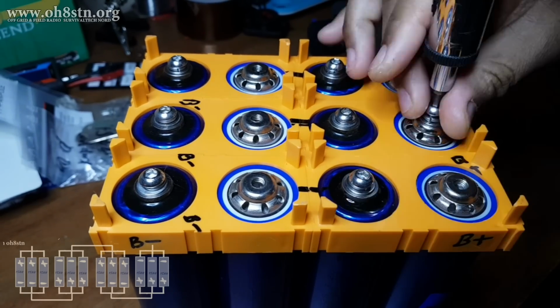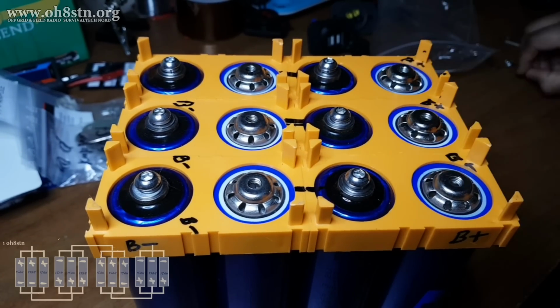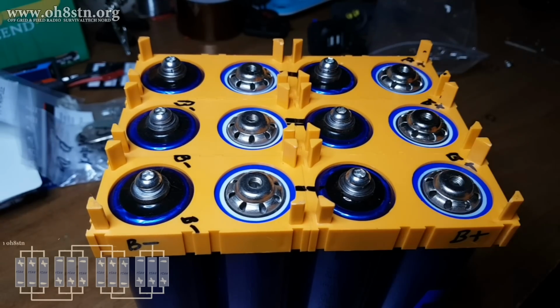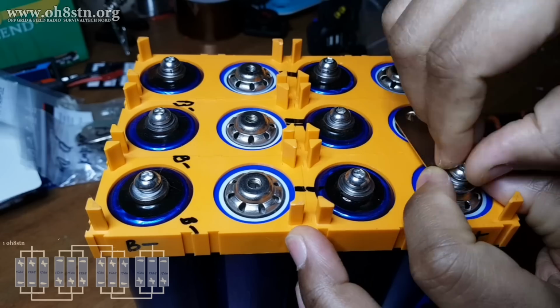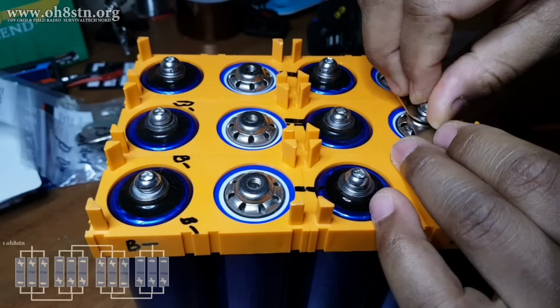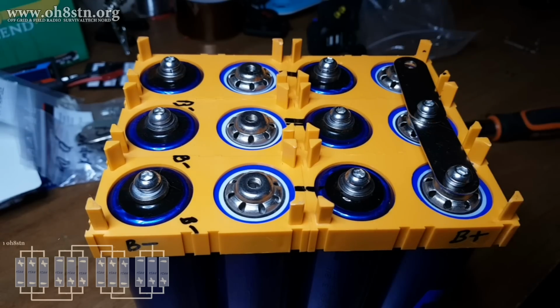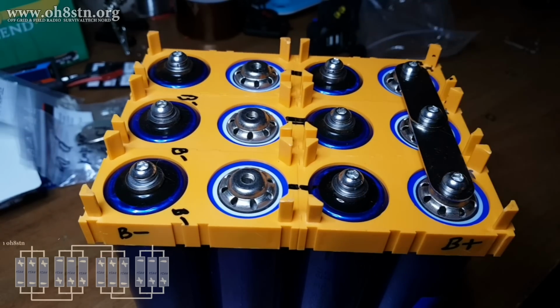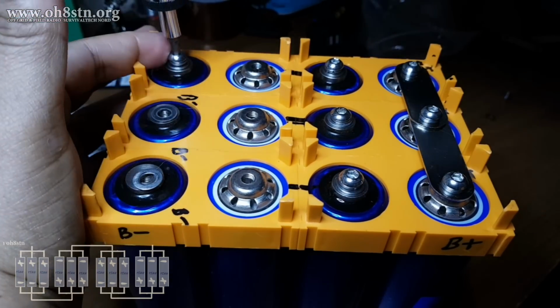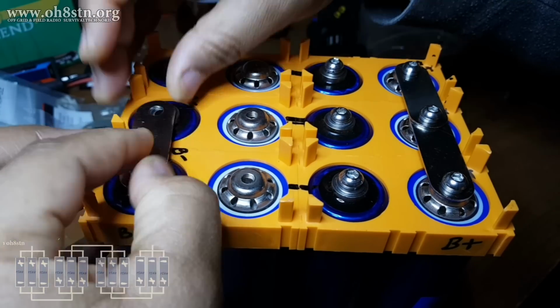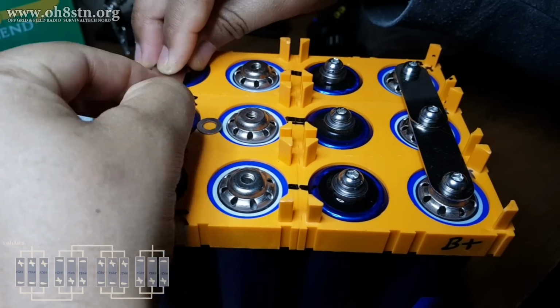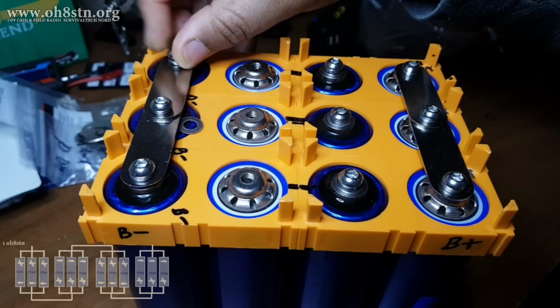So let's go ahead and install the bus bars. I'm going to use a single layer of pure copper nickel coated bus bars. It's very important to pay attention to the order we install them in. If we install the wrong bus bar without having protected the inner cell next to it, we could short out the pack.